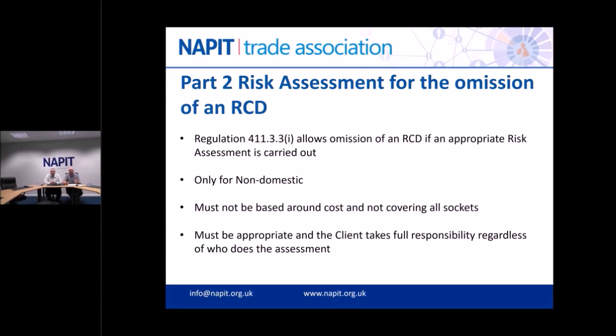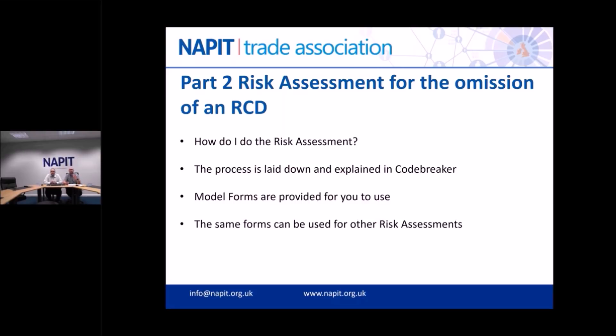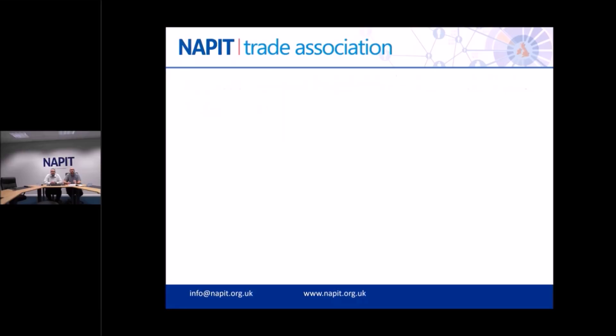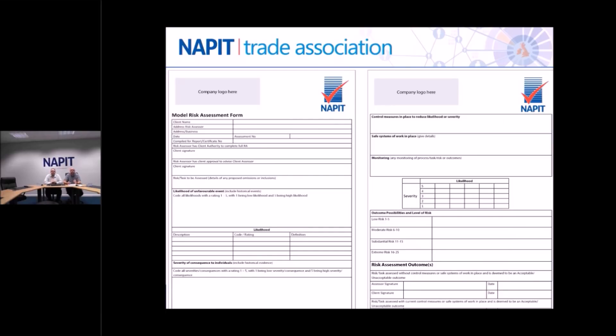For an inspector doing a condition report and finding a socket outlet without RCD, you've got to decide on coding based on the risk assessment. The first question to the duty holder is: is there a risk assessment in place? If yes, you can give appropriate codes. If not, you need to look at how to have them complete the risk assessment. The Code Breaker has all this laid down with sound advice, and we've also provided model forms for you to use for these and other risk assessments.